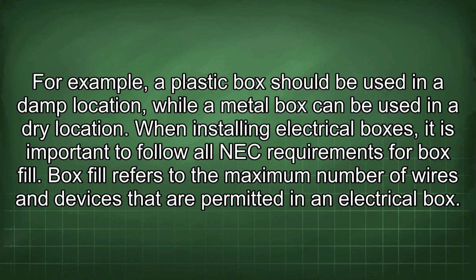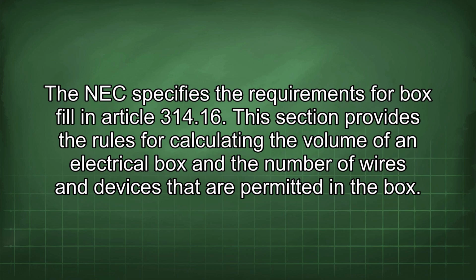When installing electrical boxes, it is important to follow all NEC requirements for box fill. Box fill refers to the maximum number of wires and devices that are permitted in an electrical box. The NEC specifies the requirements for box fill in Article 314.16. This section provides the rules for calculating the volume of an electrical box and the number of wires and devices that are permitted in the box.